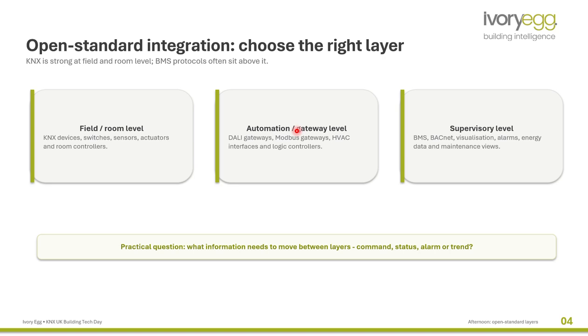Open standard integration is about choosing the right layer. So KNX is strong at the field and room level. BMS protocols often sit above it. So you can consider, for example, the protocol BACnet at the supervisory level and KNX at the control and field level. The question here is, what information needs to move between layers - command, status, alarm, or trend? We should be prepared for that during the design and programming.